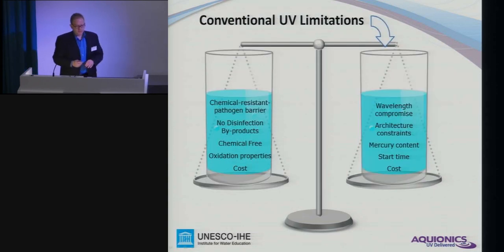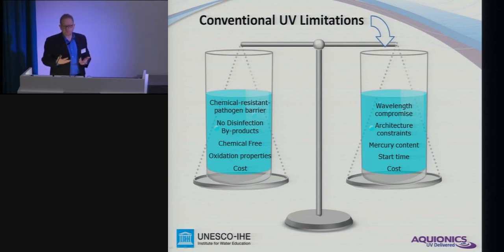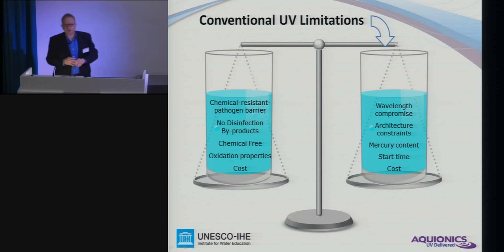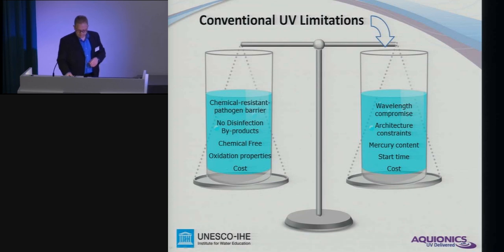On the flip side, we do have a wavelength compromise, which I will explain. We have some architecture constraints because all the lamps tend to be cylindrical and rather long, so we basically design the unit around the consumable of the product, which is really a little bit weird of a concept. Another flip side is the mercury that is in the lamps. The start time in terms of warm-up and also cooling down means you cannot just switch on and off without compromising the lamp life. And compared to other options, it could be quite costly depending on the availability of the consumables.